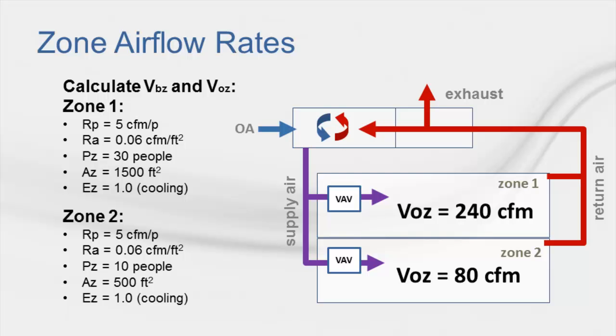In this example, a VAV system supplies cool air to each zone from the ceiling, so the zone air distribution effectiveness is 1.0. As a result, V sub OZ equals V sub BZ. Using the equations for calculating zone air flow rates, zone 1 requires 240 CFM of outdoor air, and zone 2 requires 80 CFM of outdoor air.